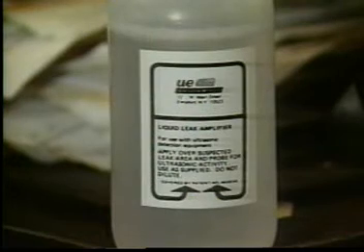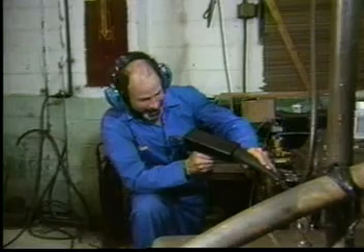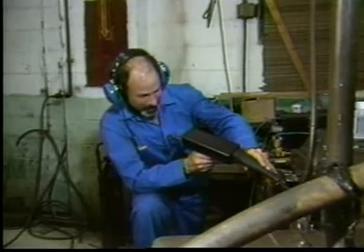The liquid leak amplifier is a low surface tension liquid. Poured over a suspected leak site in small amounts, it forms bubbles. These bubbles collapse, creating ultrasound which is distinctive and recognizable. If you've used a bubble test before, you'll appreciate the difference hearing, not just seeing, can make, especially when there are several leak sites or inaccessible areas to be checked.